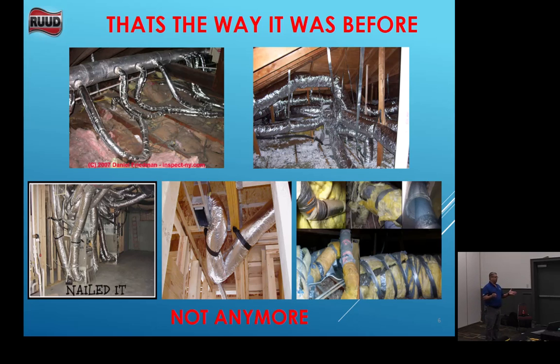Because if you go out there and you see this ductwork in a system, typically we've talked about 400 CFM per ton for years, right? What are we talking about with today's equipment? Anybody know? 350. It's kind of what we're looking at, okay? Sensible and latent temperatures have drastically changed. We used to be at 75 sensible, 25 latent heat removal. Now we're lucky if we're at 85, 15, okay?